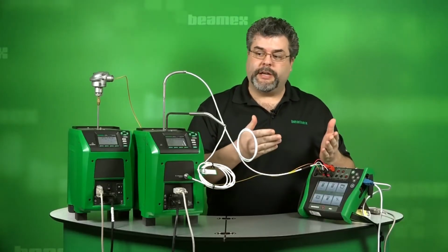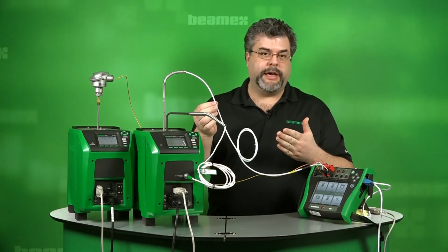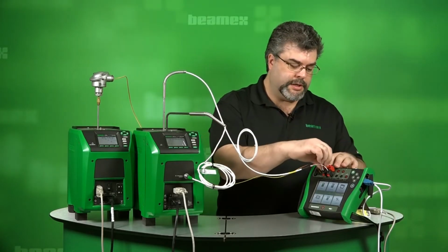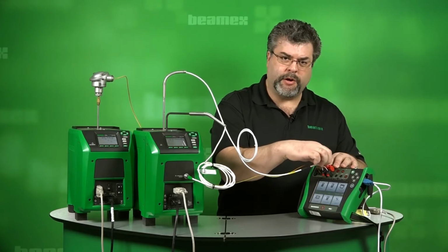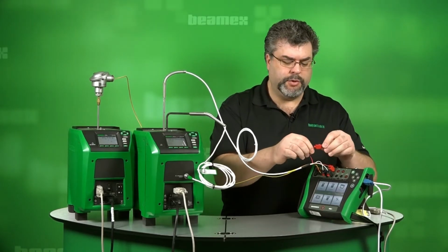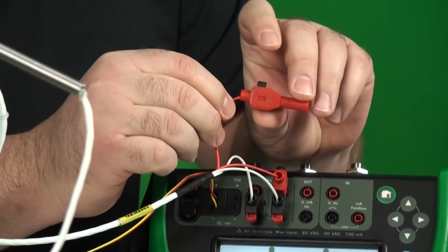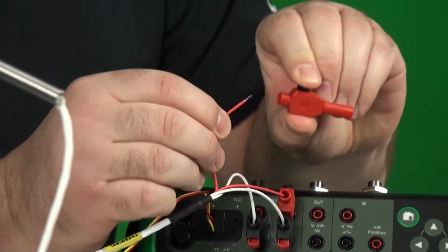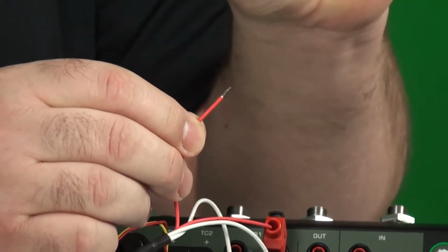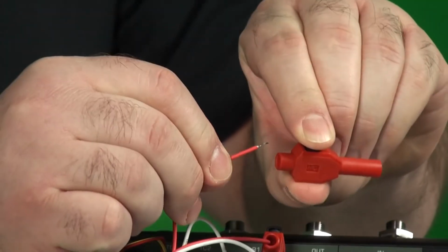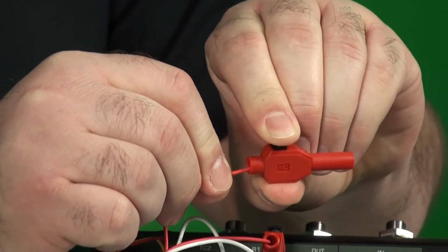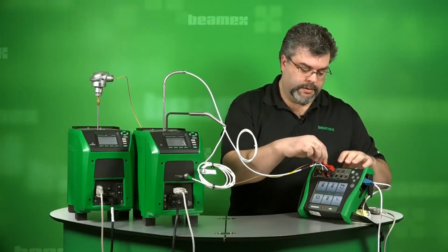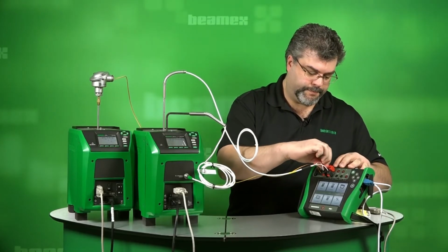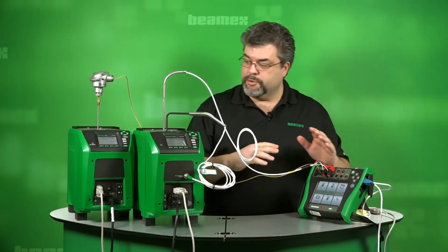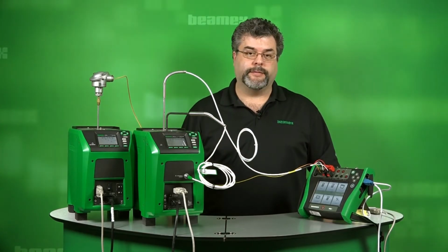On the RTD side, you may have connections already made, but what I'm using here, I have a 4-wire RTD, and I'm using one of our bare wire connectors. This has a little button here, and this allows you to convert a bare wire to a banana plug. Very convenient. Let me get that plugged back in. So those are all the connections that we have going on here.